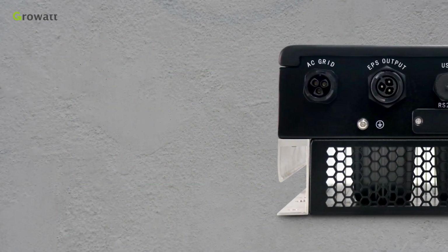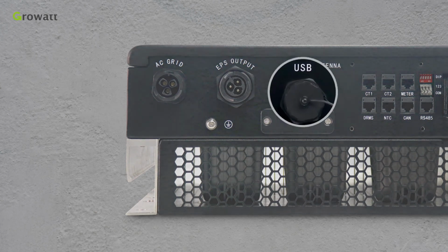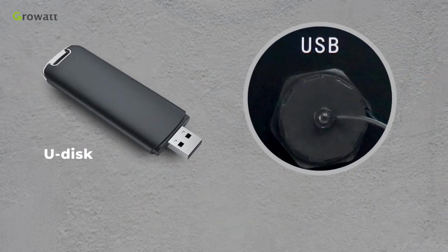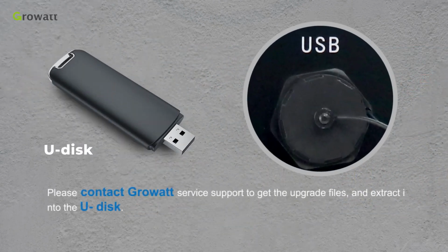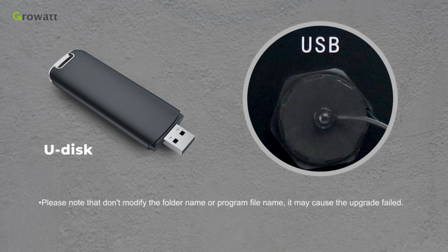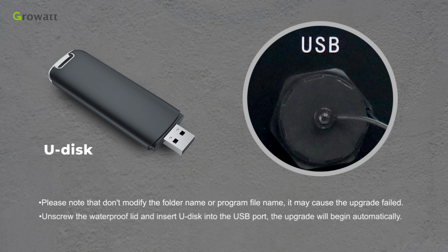User can upgrade the inverter's firmware via the USB port by using a U-Disk. Please contact Growatt service support to get the upgrade files and extract them into the U-Disk. Please note that you should not modify the folder name or program file name. It may cause the upgrade to fail. Unscrew the waterproof lid and insert the U-Disk into the USB port. The upgrade will begin automatically.